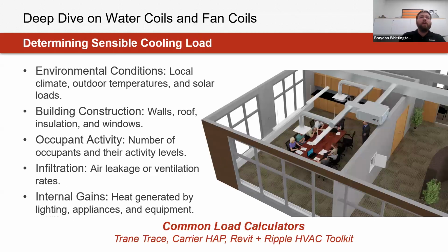And how do we really determine that? Well, there are so many different variables that can be taken into account when looking at what's driving sensible loads within a system, whether it be environmental, infiltration, internal gains, or how many occupants are within the space. You'll see those people in this office having a meeting right now, and how much sensible offset is going to be required from them. There are lots of different formulas or calculations that would need to be taken into account for this. But more often than not, this is going to be done from different load calculators for a system. They're effective because they use the most up-to-date codes for calculating some of these different variances, to determine that performance.